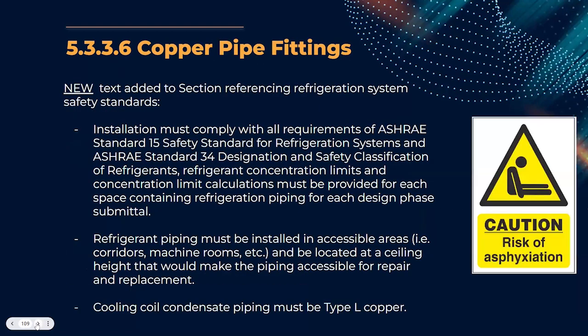There's been specific reference now made to ASHRAE 15 and 34 in terms of added refrigerant safety standards, especially as it relates to volume concentration limits and the routing of refrigerant-containing piping, which must maintain accessibility so that you can mitigate against any sort of leaks. And one minor update is that cooling coil condensate piping must be type L copper. Next slide, please.